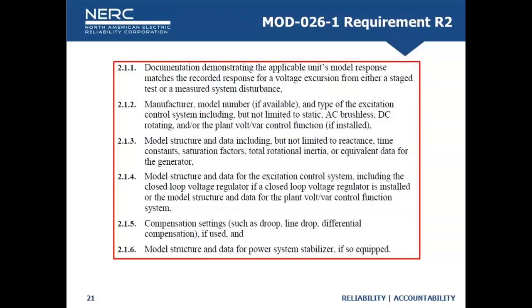I'm going to push the envelope here a little bit and push the status quo, and say simply showing that a simulated response matches actual response for a bump test or a voltage step test is insufficient in meeting the standard. I don't work in compliance, but in my opinion, that's not enough, because it doesn't verify that the model is accurate.